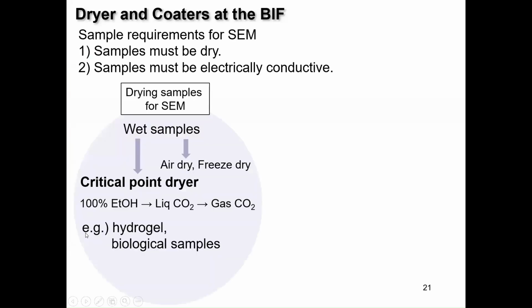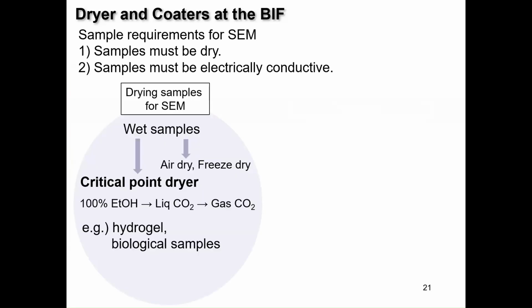I want to switch to the dryer and coater. Here are the sample requirements for SEM: because the SEM column is under high vacuum, samples must be dry. If there's any liquid, it gets vaporized and contaminates the electron column. Samples must also be electrically conductive. If your samples are wet, researchers air dry, oven dry or freeze dry. But some samples are really sensitive to heat or the drying process. Then we have equipment called the critical point dryer.